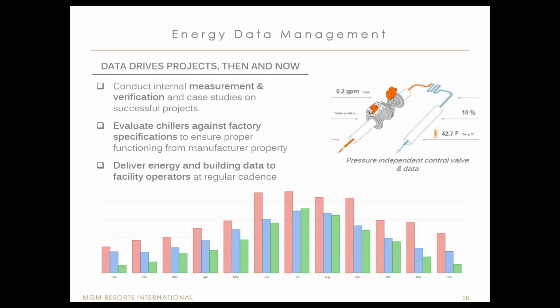And then finally, we are able to do measurement and verification. I've got a generic graph here, but this is real data for 2017. One of our buildings got a major upgrade in the control system in the central plant, along with VFDs on chillers and enabling heat exchangers for free cooling. You can see red being baseline, blue being predicted, and green being actual energy consumption by month for that property. This property has become the absolute sales pitch test case for our group when it comes to doing upgrades across our properties for control systems and such.